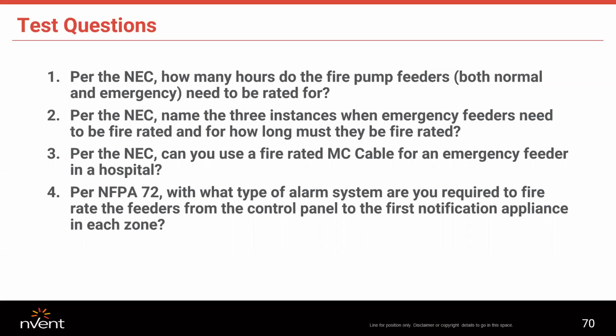I just want to add one more time, for fire pump feeders, the sprinkler system is not an option. Whether you have it or not, that feeder has to be fire rated, both normal and emergency.